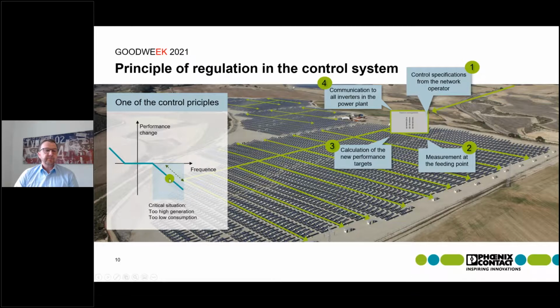You have the power output controlled on the grid frequency. If you have a rising frequency, you have to reduce the power output of your PV plant because you have too high a generation, or, the other way around, the consumption in the network is too low. Therefore, you have to reduce the power. This power handling, this feed-in management, is handled by the feed-in management system at the grid connection point.